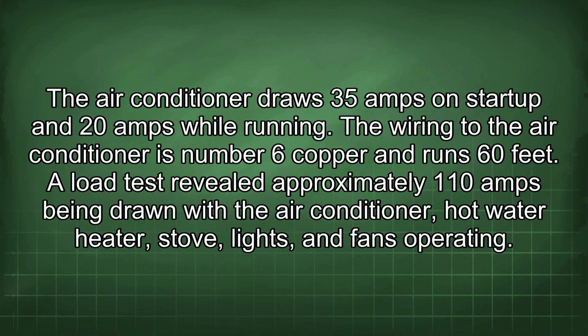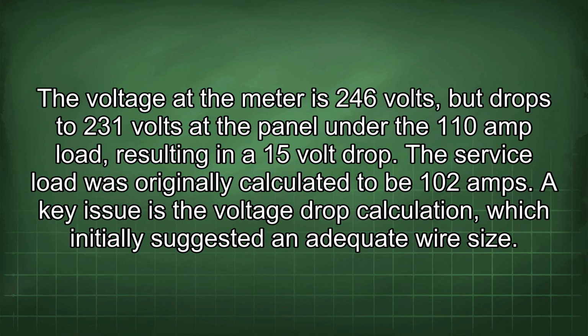The air conditioner draws 35 amps on startup and 20 amps while running. The wiring to the air conditioner is number 6 copper and runs 60 feet. A load test revealed approximately 110 amps being drawn with the air conditioner, hot water heater, stove, lights, and fans operating. The voltage at the meter is 246 volts, but drops to 231 volts at the panel under the 110 amp load, resulting in a 15-volt drop.